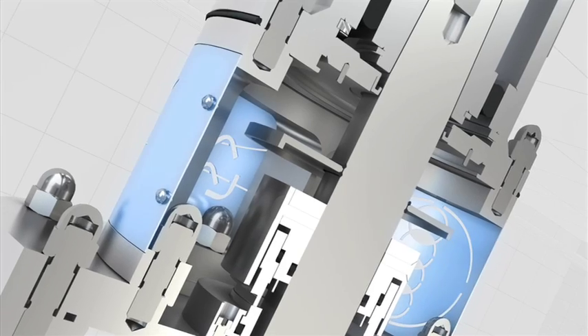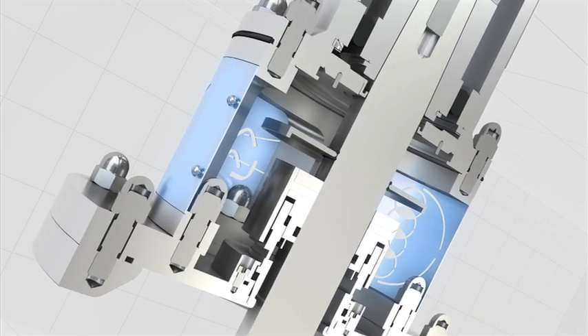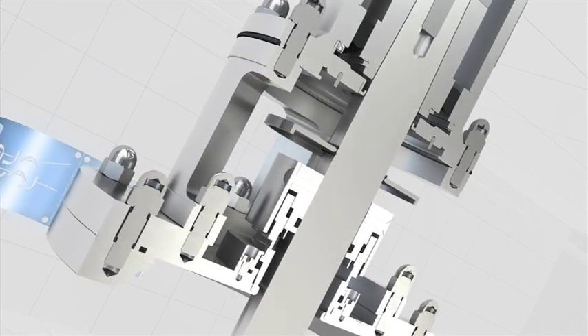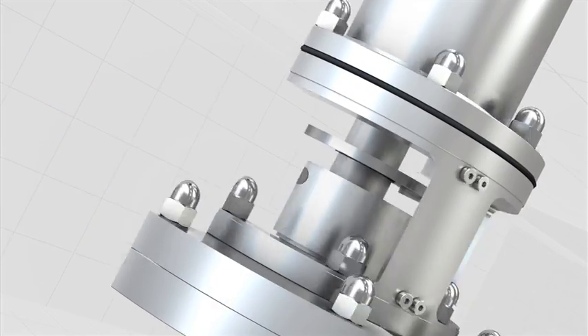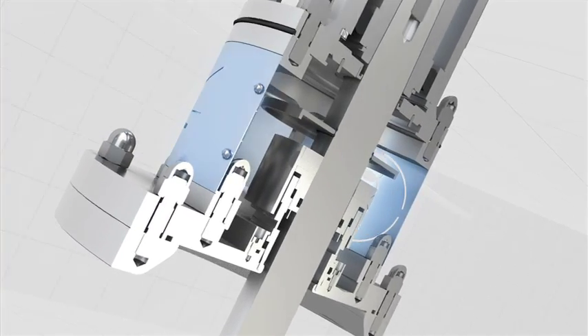The lantern placed between the bearing frame and the mounting flange serves as spacer for the seal arrangements and provides good inspection properties. It is possible to change the seal arrangements from outside the tank without human entry into the tank.